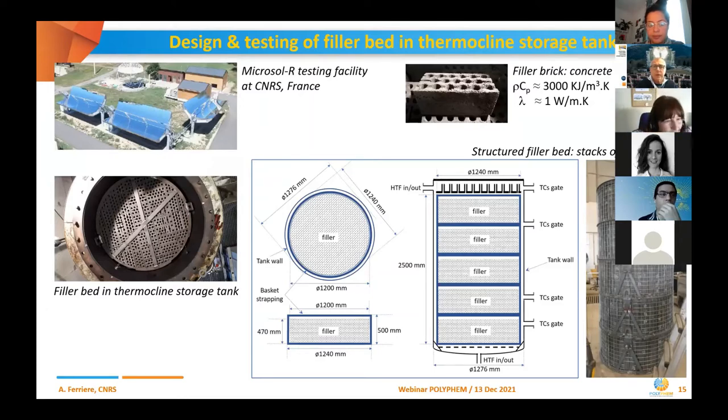And then the next and last slide is about the design and the testing of the filler bed in the thermocline storage tank. So the philosophy of POLYPHEM is to use a structured filler bed, which means that the material is presented in the form of bricks, and the bricks are stacked and arranged in the tank, as you can see in the picture here.